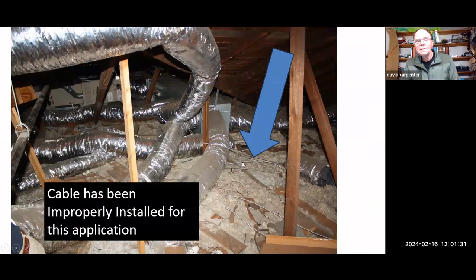This is the walkway. When you have a bus duct or an HVAC unit in an attic, or anything electrical up there, you have to build a walkway over to it so nobody walks through the ceiling. But running the MC cable right over it like this is a real problem because nobody sees it. Even the MC cable, if you look here, was pinched because they had it in such a bind. This is just poor workmanship, the only thing you can say.